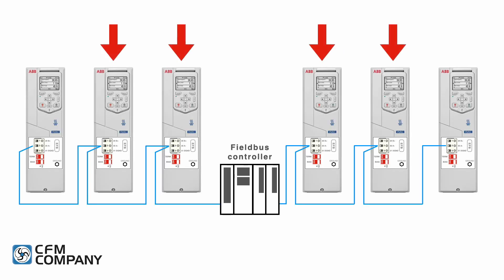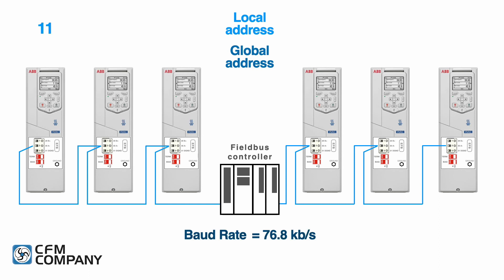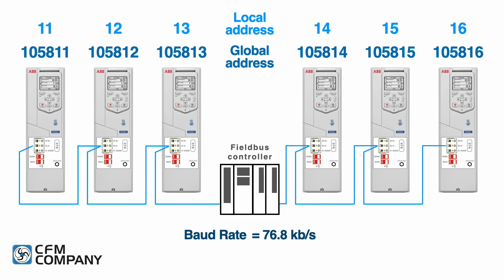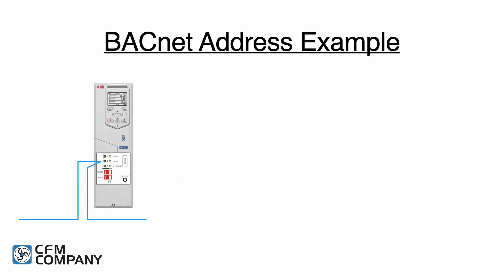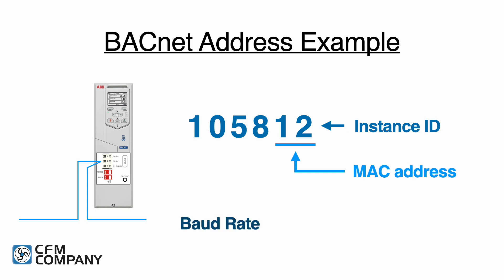If the drive is not at the end of the network, both the term and bias switches should be off. Each device on the network requires a unique MAC address and instance ID. Ask the building automation contractor for a list of addresses for all of the drives on the project. You will also need to know the network baud rate. For this video, we will use the instance ID of 105812, where the last two digits of the instance ID is also the MAC address. The network baud rate will be 76.8 kilobits per second.